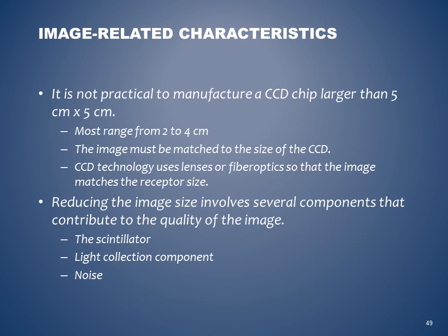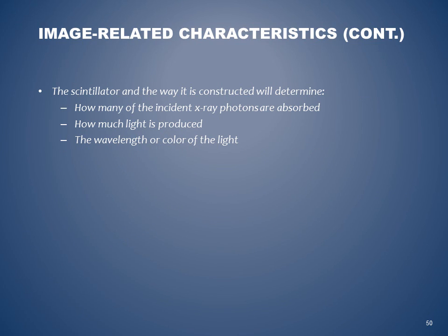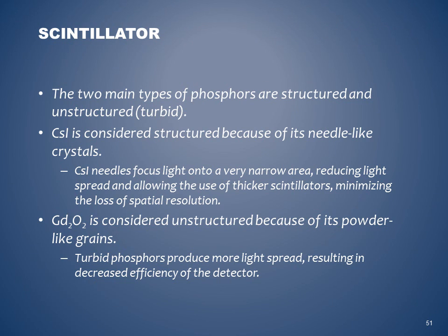Image-related characteristics. It is not practical to manufacture a CCD chip larger than 5 centimeters by 5 centimeters. Most range from 2 to 4. The image must be matched to the size of the CCD. CCD technology uses lenses or fiber optics so that the image matches the receptor size. Reducing the image size involves several components that contribute to the quality of the image: scintillator, light collection component, and noise. The scintillator and the way it is constructed will determine how many of the incident X-ray photons are absorbed, how much light is produced, and the wavelength or color of the light.